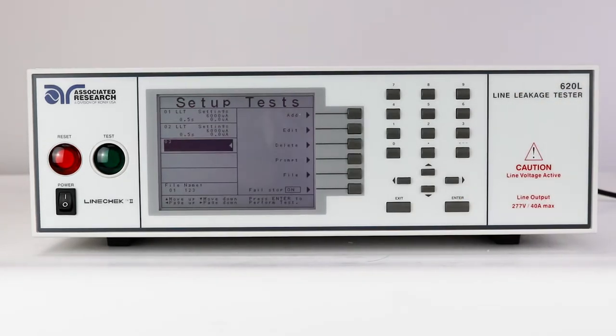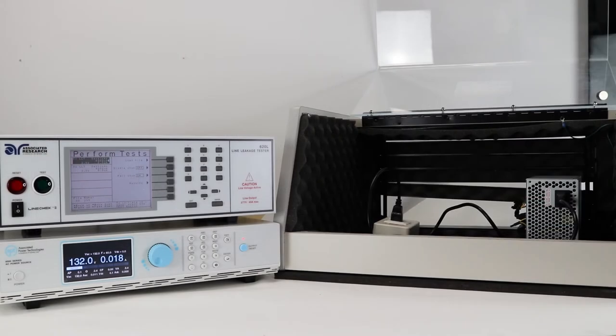Press enter to save the changes. In the video, we have set up an earth leakage current test under normal conditions followed by an earth leakage current test with an output neutral fault. We will be using the IEC 60950-1 measuring device. Next, we're going to connect an external power source to the Linechek. This will allow you to run power through the Linechek to power up the DUT during the line leakage testing. Then, we'll connect the Linechek to the DUT and run a test sequence.